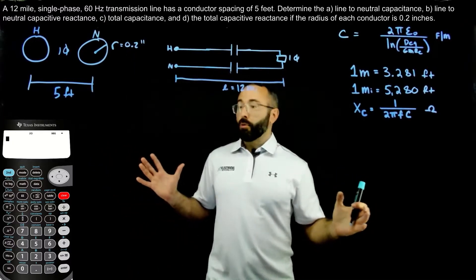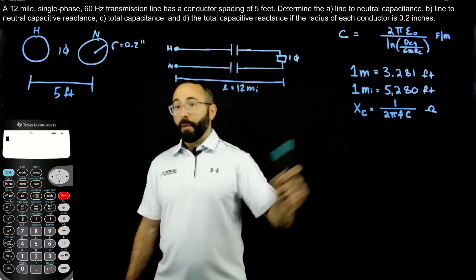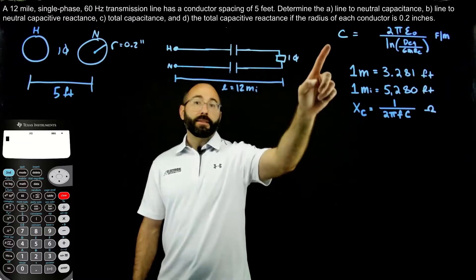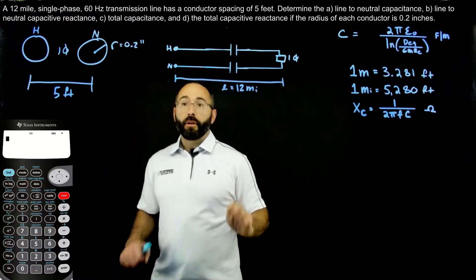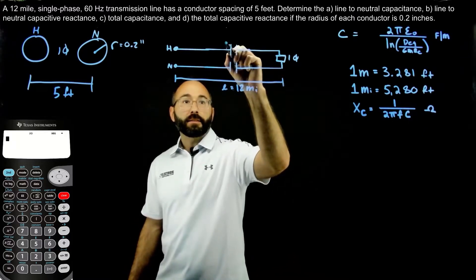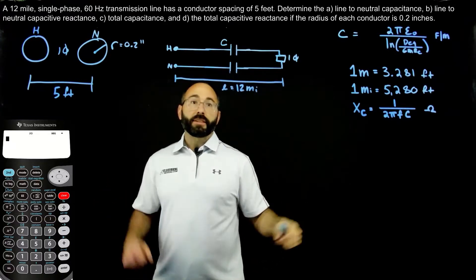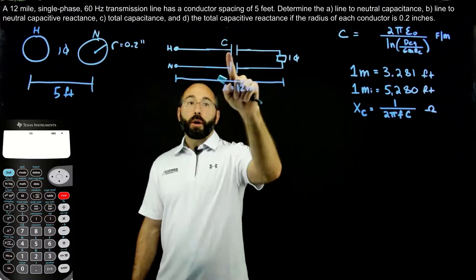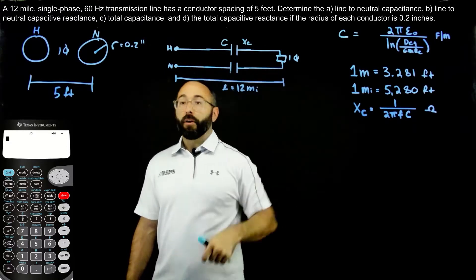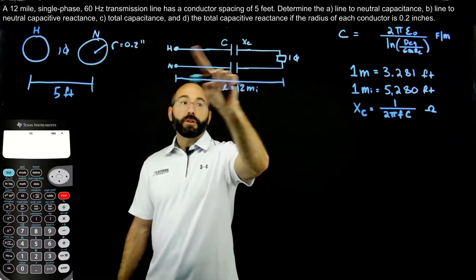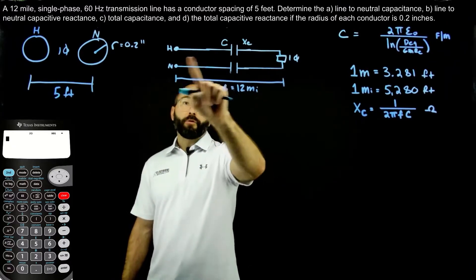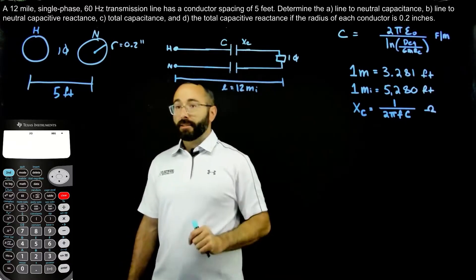This is the same problem as the last one when we were solving for inductance and inductive reactance — instead we're solving for capacitance and capacitive reactance. Just like before, when dealing with a single phase transmission line there are two sets of values. We have the one-way length, same as the line-to-neutral, same as the average, same as the per-phase amount — that's the capacitance from the hot conductor up into the load, essentially just one conductor. For C and D we'll solve for the total capacitance and capacitive reactance from the hot conductor to the load and back through the neutral through the power source, accounting for both conductors.